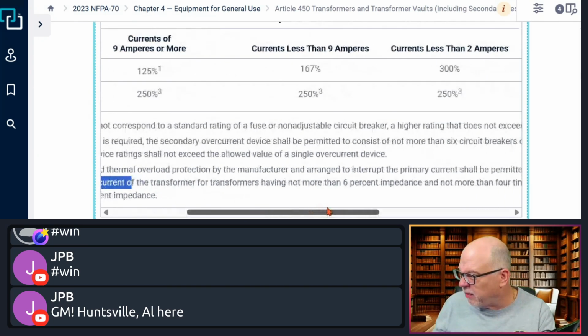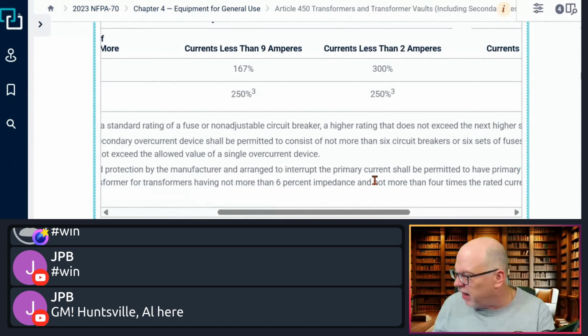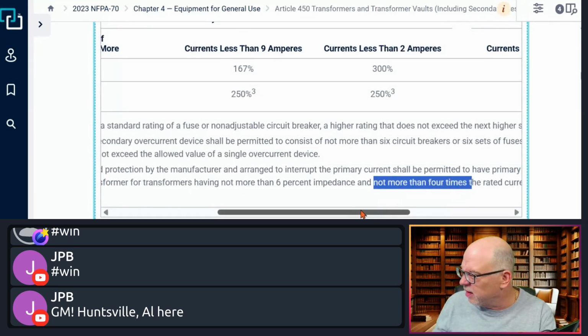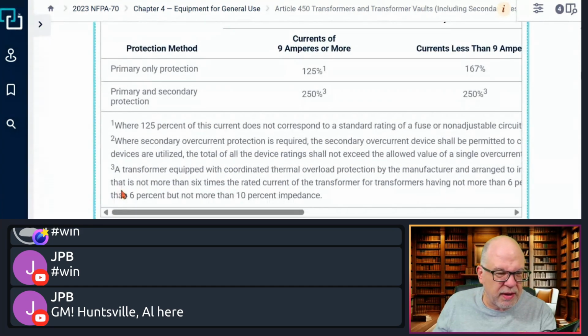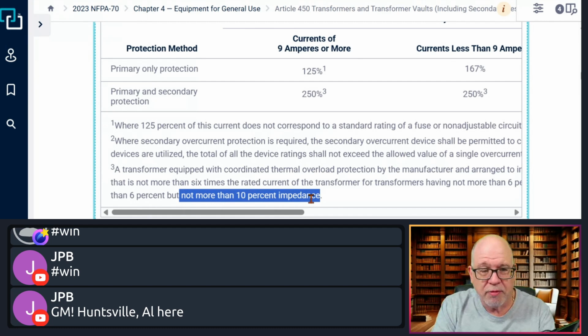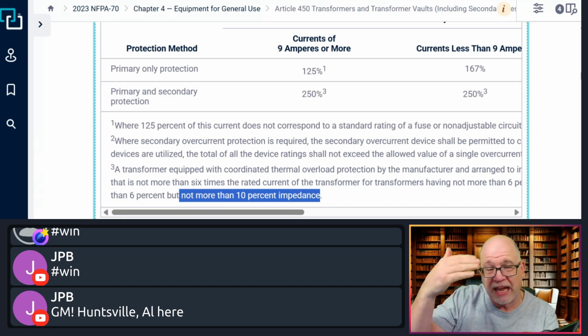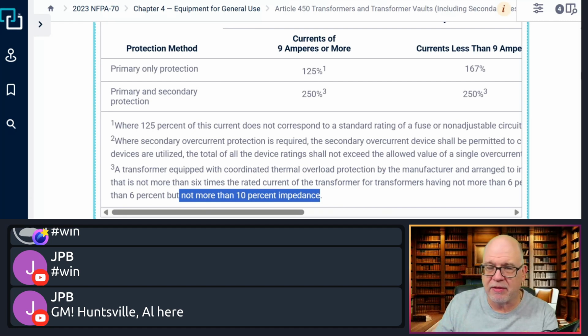Now, what happens if I have impedance that's higher? Well, it says not more than 4 times the rated current, okay? Not more than 4 times the rated current, where the impedance is more than 6% but not more than 10%. That would be an extremely inefficient transformer. Probably not going to find any like that that are going to be more than 10%. Okay, so this allows you to deviate from the 250, but we don't have the same next size up rule. We just have, look, I can use 250, not exceed 250. I could go up to 250% on the primary side if I wanted as a maximum. I can't exceed 250. But then I have these other allowances depending on the impedance of the transformer. So I can go either 6 times the rated current of the transformer if it's not more than 6% impedance, or up to 4 times the rated current where it's not more than 10. So your 10 and 6 are your thresholds.